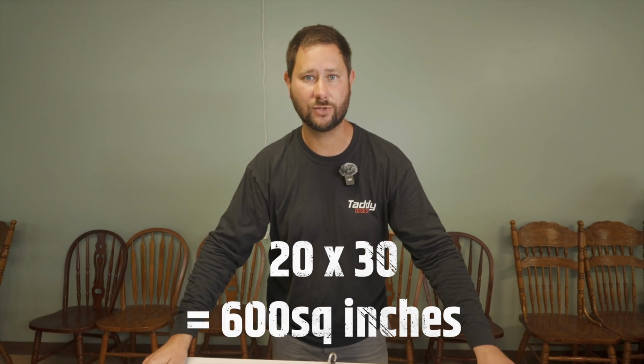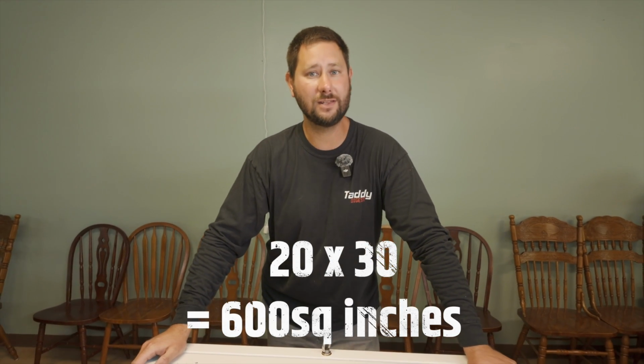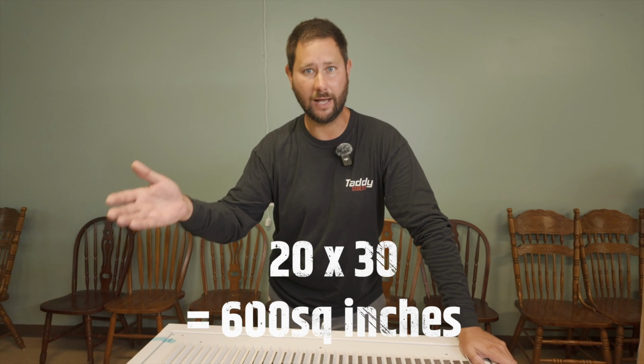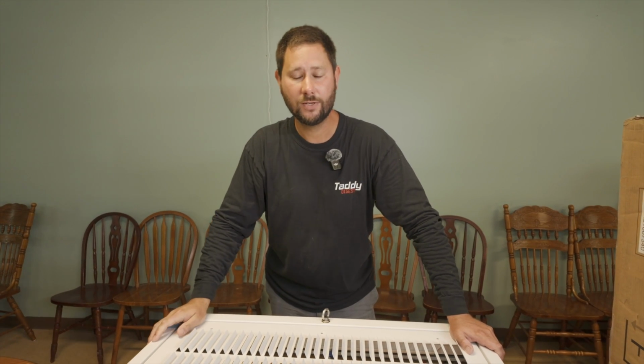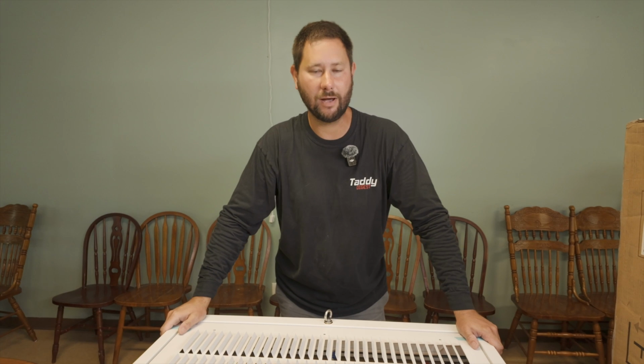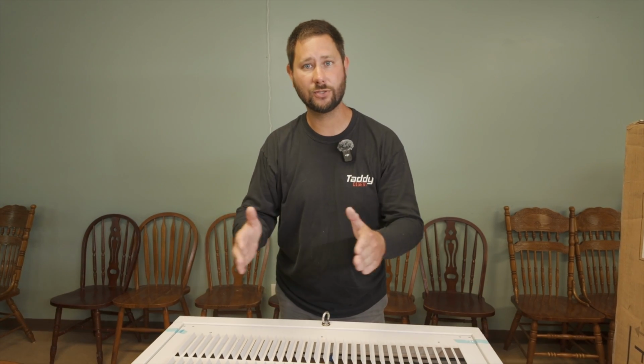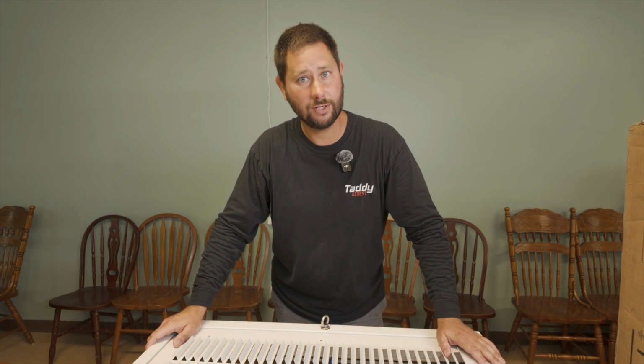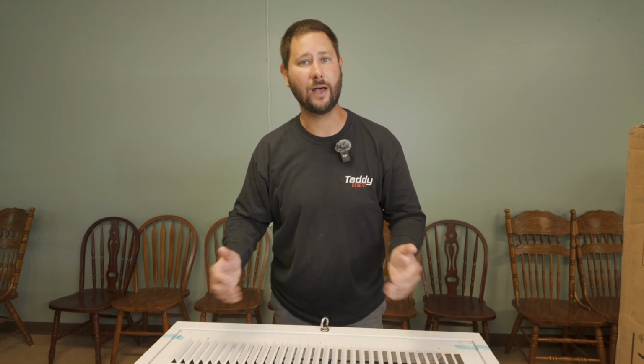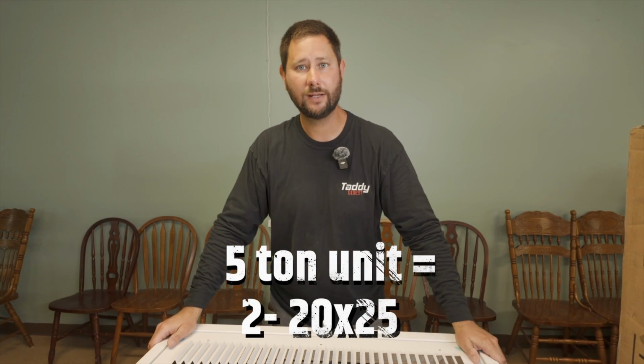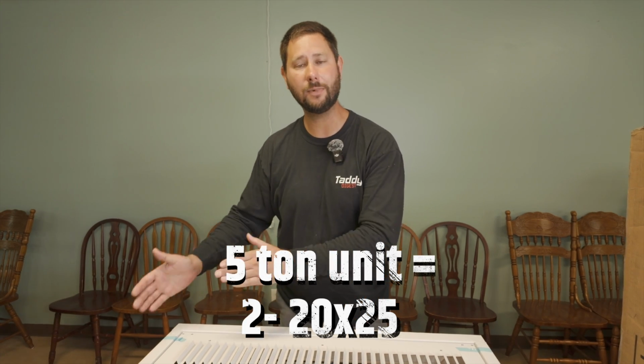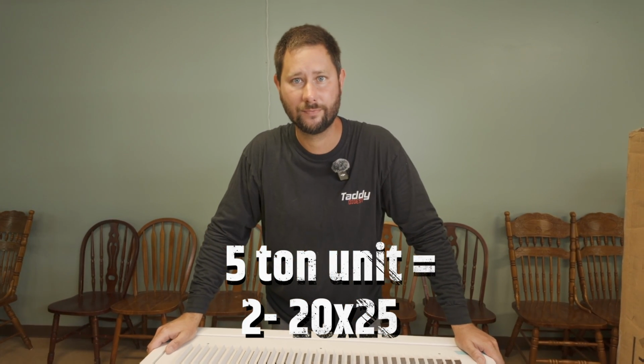Then we take the return grills that we have, which we have 20 by 30 right here. This would be 20 times 30, which would equal 600 square inches. So if we divide 600 by 200, that's only good enough for 3 tons, right? So we would have to use 2 of these 20 by 30s. But to get closer to that 1,000, what we could do is use 2 20 by 25s. So if I was installing a 5-ton unit, I would need 2 20 by 25 return grills.